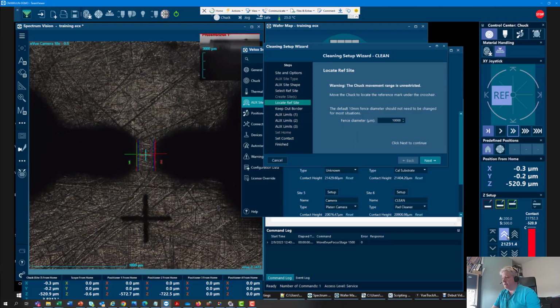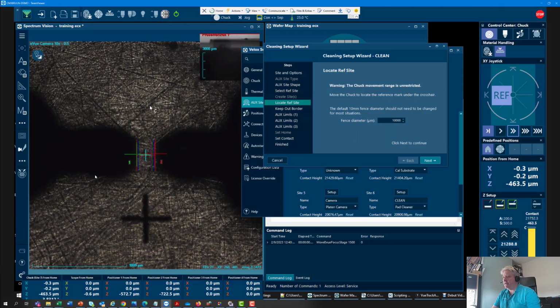So yeah, I'm in this region here. We're not going to focus on here, just so I know that it's physically present. And I have this fiducial marker. It's on the AUX chuck fence, a distance away from my probes, so I can see it. The probes don't obscure it. And now it wants me to determine the size of my cleaning media. So this is saying I'm allowed to be within 500 microns from the edge when I do my automatic movements, and my automatic movements will be defined by the probe size in X and the probe size in Y. The idea is it's going to make a 50 micron step each time it moves horizontally, and a 300 micron step when it moves vertically to keep itself away from the detritus from the previous cleaning cycle.